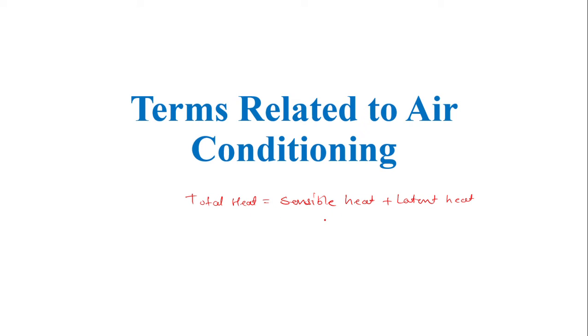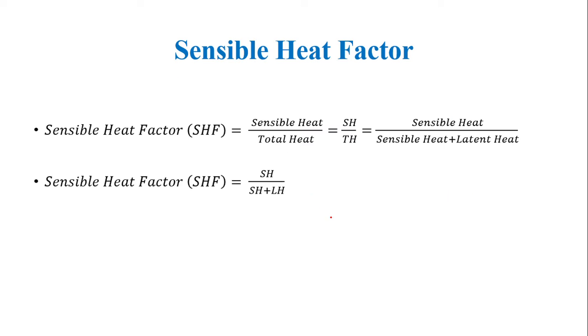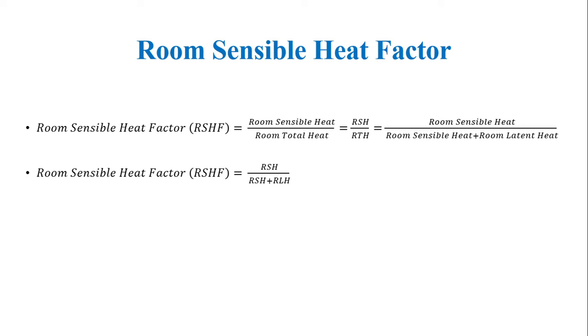We will see these terms one by one. The first is the Sensible Heat Factor, also known as SHF. This is the ratio of sensible heat to the total heat — sensible heat divided by total heat — where total heat is sensible heat plus latent heat. Mathematically: SHF = SH / (SH + LH), where SH is sensible heat and LH is latent heat.